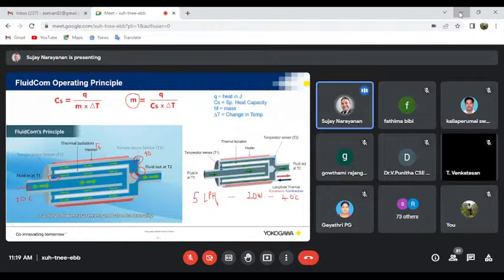Okay, and the FluidCom can talk wirelessly to the PLC, publishing the data from the FluidCom, that is the current injection rate values, over wireless. And in this particular implementation, we are using the ISA 100.11a wireless protocol to publish the data over here. Okay, so we have a completely closed loop or cascaded or ratio control between the production and the chemical injection. Earlier, the chemical injection was totally independent and the well production was totally independent. Now we are tying up the corrosion and everything over here.